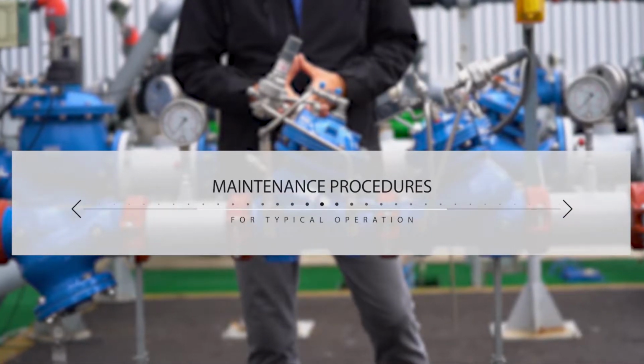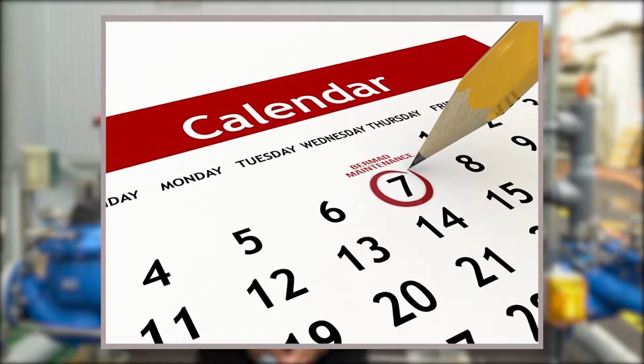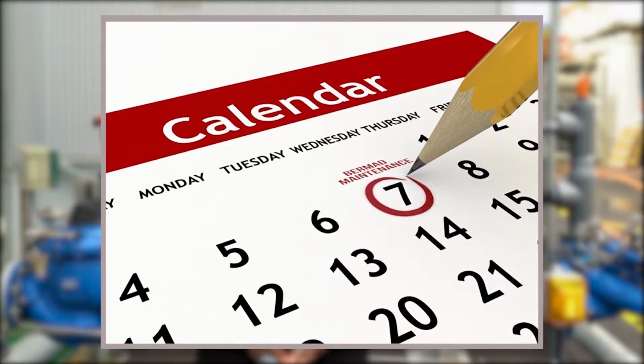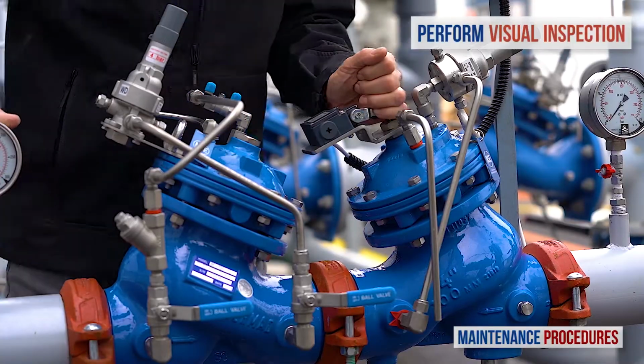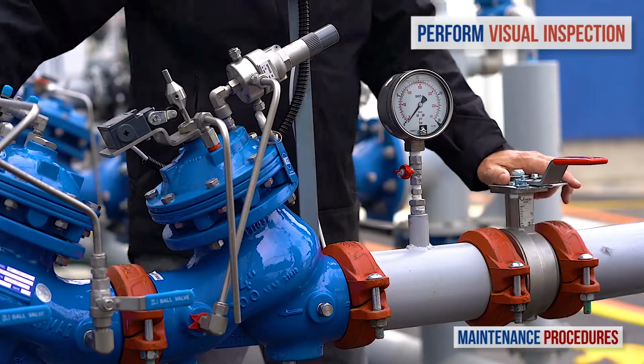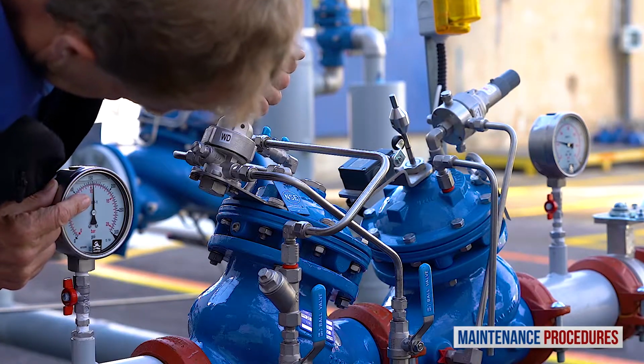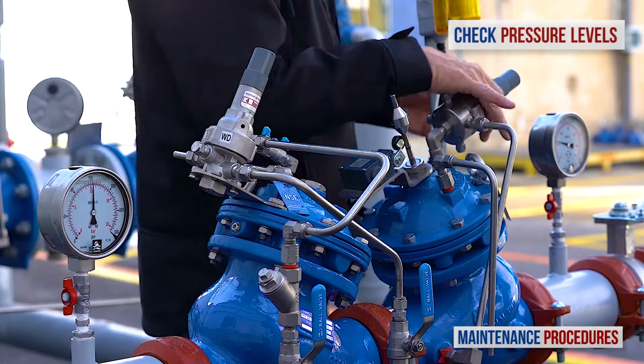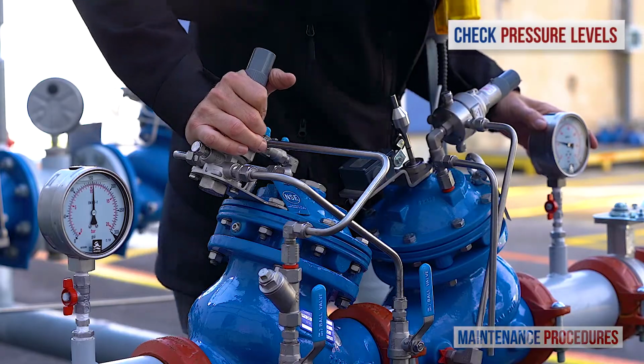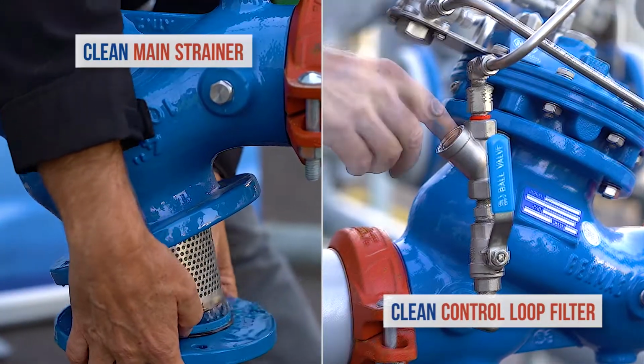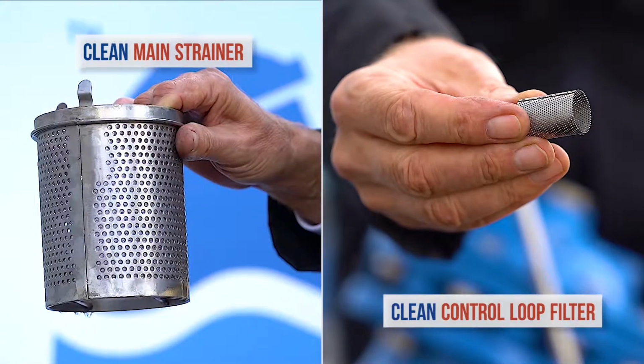Now let's discuss maintenance procedures for the Bermad pressure reducing station with shutoff valve. Note that your schedule for preventative maintenance depends on actual conditions of use and the station's environment. Here we discuss a schedule suited to a valve operating under average conditions. On a weekly basis, perform a visual inspection of the station and check for leaks and external damage. In addition, observe the unit's pressure gauges to make sure that the pressures upstream and downstream are as they should be. Once a year, close both the upstream and the downstream isolation valves and clean the main strainer and the valve control loop filter. Every 3 to 5 years, inspect the internal condition of the pressure reducing valve.